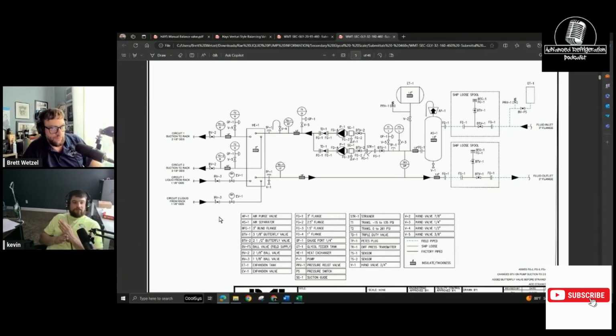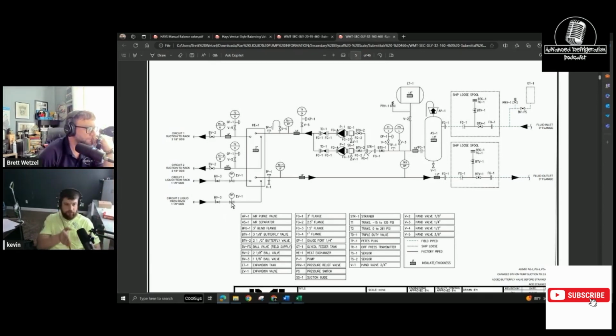Are they crisscrossed? No. So this is for everybody at Costco. If you look at the dual circuited heat exchangers, so you've got say suction line, liquid line, suction line, liquid line. You would think the liquid line's going on the bottom, suction line's coming up the top. It's the opposite. Is it really? The liquid line on the right-hand side is coming out the suction line on the left-hand side. They're crisscross piped. And there's one little thing on the pump skids from Zero Zone with a little picture on there, the size of a Polaroid, that explains this. That is the first thing I do if I see people piping it. I mark them. I go, wait a minute.